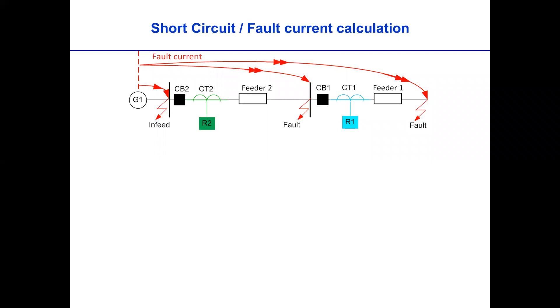The first thing we need to do in protection is calculate the fault current, because that fault current will determine the setting of the current. For example, we have three faults at each busbar.